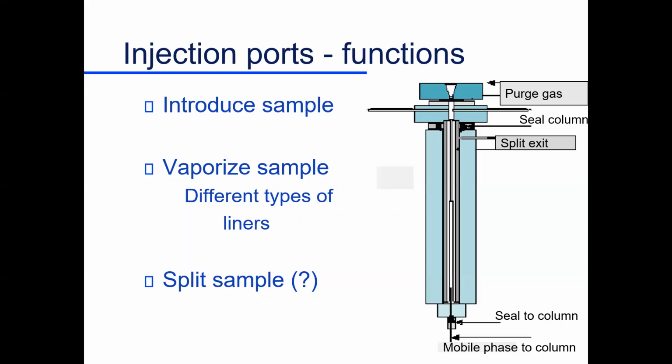And the problem is, this is a little rubber septum. It's not rubber, but it's a polymer septum. We've got to put a syringe down into here, so we need something we can put a syringe through. And this polymer can give off materials. It's going to be 250 centigrade. It can give off volatiles. It can decompose. And so anything that's decomposing up here comes down here, but then gets swept off here. So this purge gas is basically keeping the system clean. Anything that degrades up here can't contaminate our system. We put our syringe down here, we make our injection, and then some part of it, like I say, goes out again. The rest of it goes into the mobile phase.